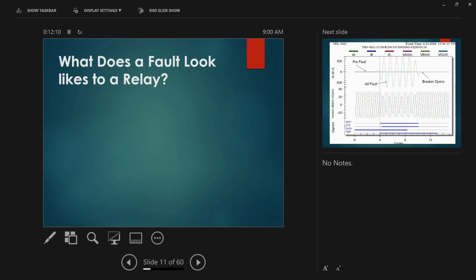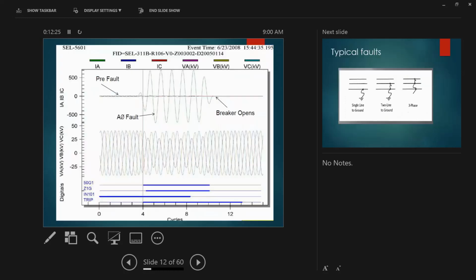So anyway, what does a fault look like on the relay? As a relay tester, you need to understand what is happening inside the relay. It should be in your head. If you do relay testing, you need to get around it. If you look at the current ABC and the voltage ABC as well: if you have a higher voltage, you have a smaller current, and vice versa. If you go to low voltage, you have higher current. That's why you have big cables and those breakers, 3,500, 4,000 amps, because it's low voltage. So you see higher voltage, low current. But let's say you have a fault in phase A.